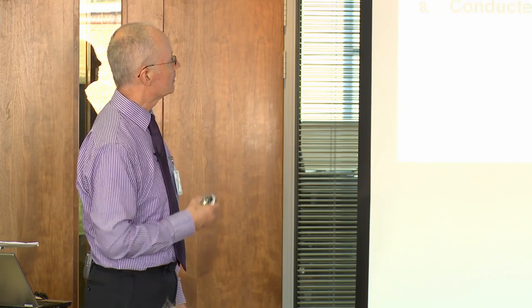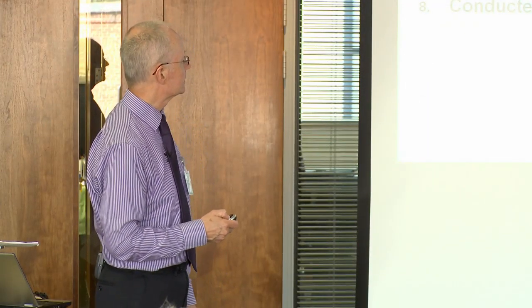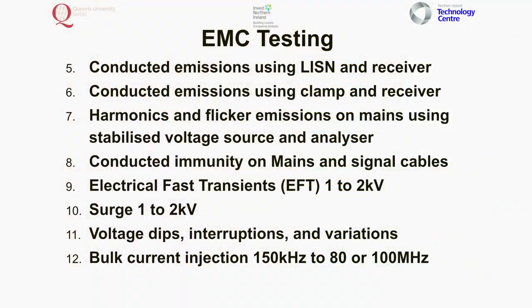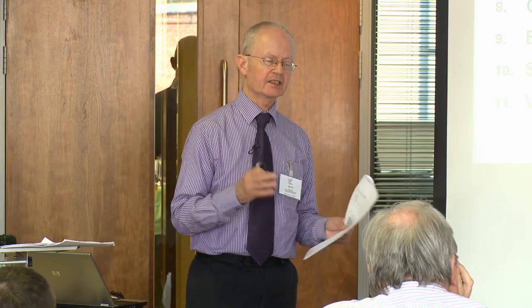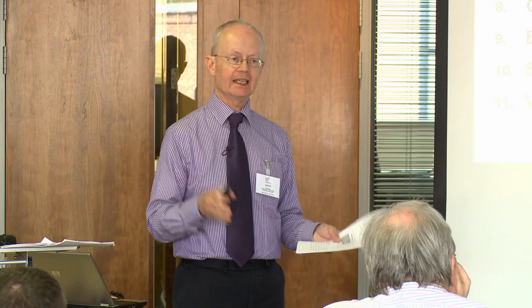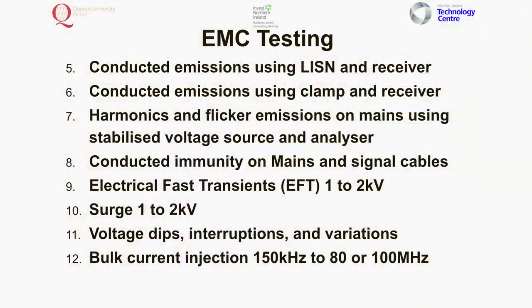Radiated immunity covers 80 MHz to 1 GHz, or now up to 2.5 GHz, using an anechoic chamber, signal generator, power amplifier, field probe to measure, and a camera to monitor what's happening. Electrostatic discharge goes up to 8,000 volts, stepped up in sequence, with two types: contact discharge and air discharge. Power frequency magnetic field testing is only done if there's likely to be a susceptibility. Conducted emissions use a LISN and receiver, or a clamp and receiver.